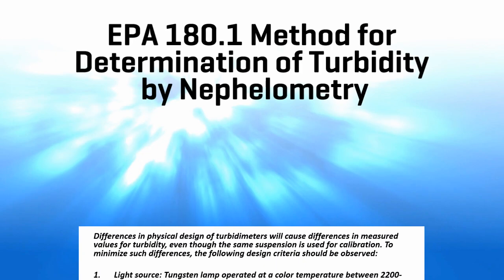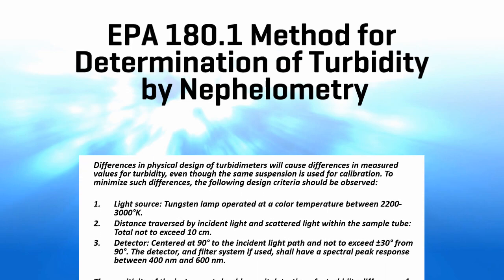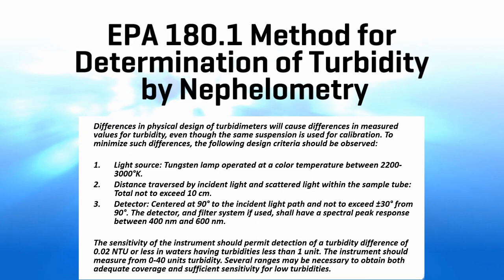So I'm not going to read the 180.1 rule to you. You can certainly go and look it up anytime you want. EPA has it right on their site, and it will basically tell you how the build of your meter that you're using to measure has to be, what the temperatures are, what the ranges are. For public drinking water utilities that are testing for compliance, your turbidity meter has to go up to 40 NTU. 0 to 40 NTU.